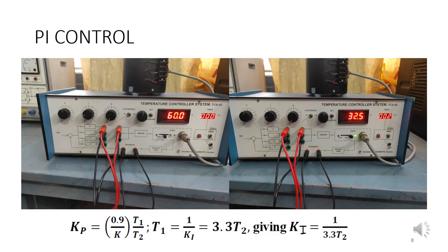For the PI controller, Ziegler-Nichols suggests values for both Kp and Ki. Starting with a cool oven, set S1 to wait and connect P and I outputs to the actuator input; disconnect R and D outputs. Short the feedback terminals and set the P and I potentiometers to the calculated Kp and Ki values (maximum Kp is 20, maximum Ki is 0.036). Set the desired temperature to 60°C, switch S1 to run, and record temperature readings. Plot the response and observe the steady-state error and percentage overshoot. Compared to the P controller, the steady-state error is reduced by adding integral control.